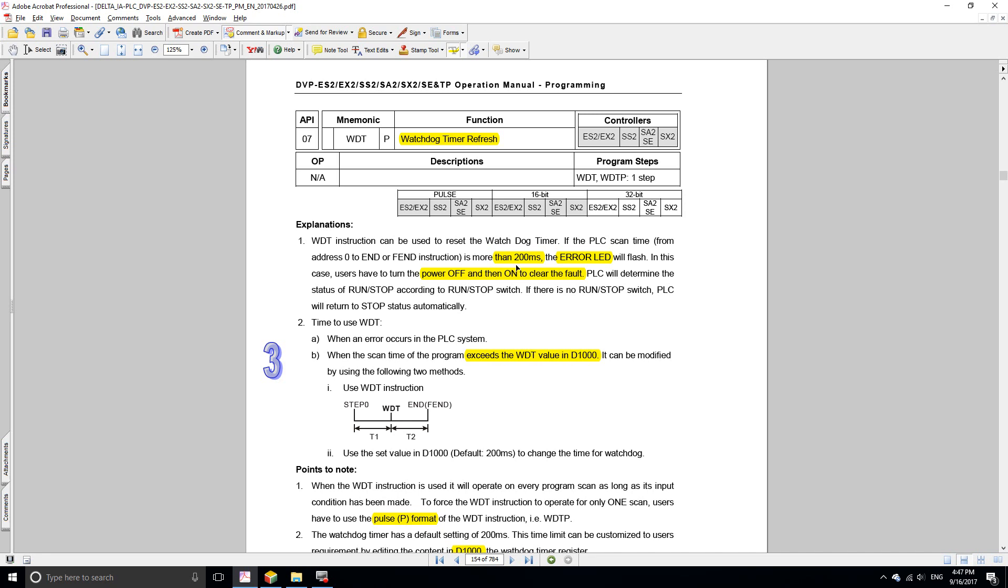That's a safeguard in case there's an error within the program. Let's say that by mistake you create an endless loop, then the watchdog timer is going to exceed 200 milliseconds and the PLC is going to stop. The error LED will flash.